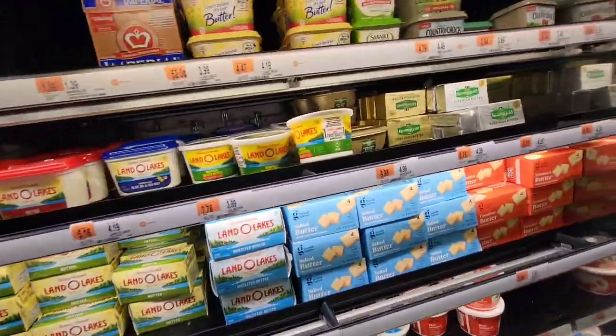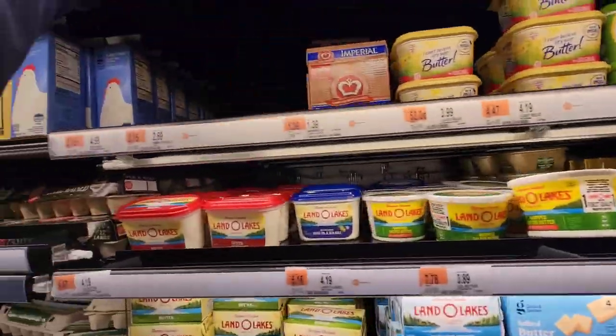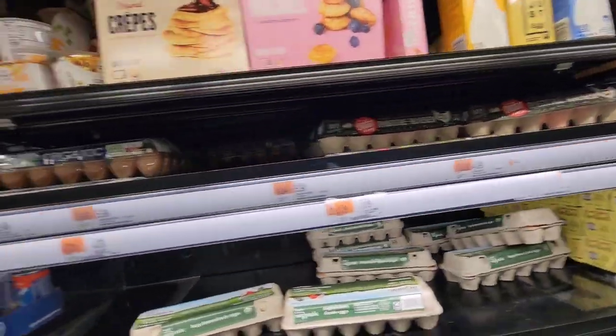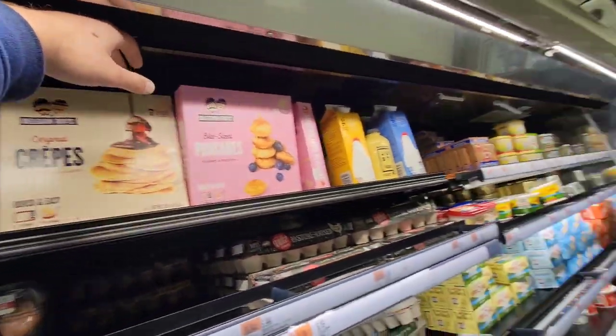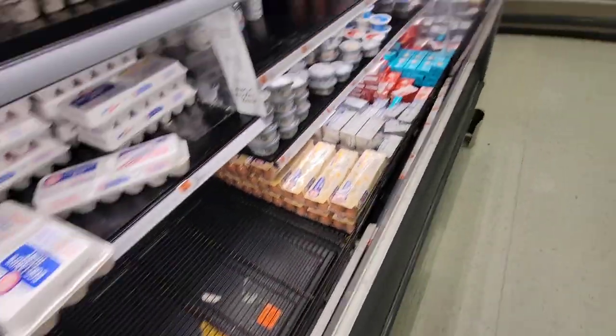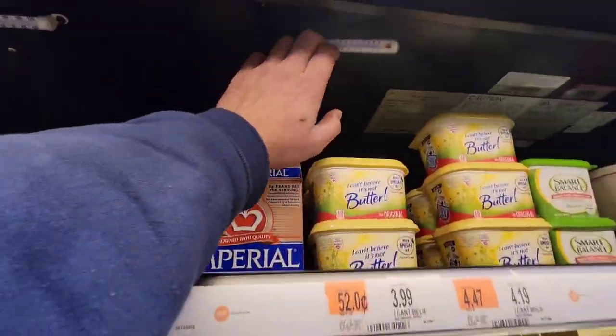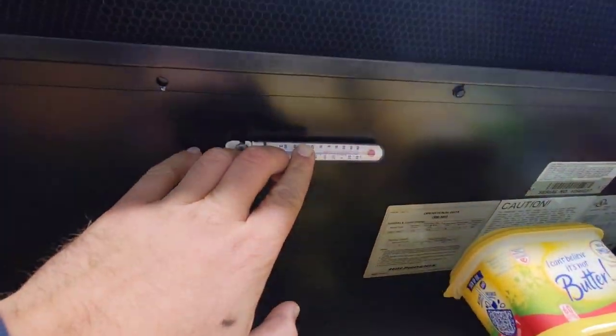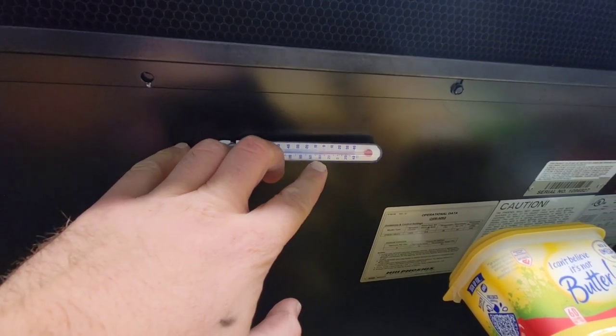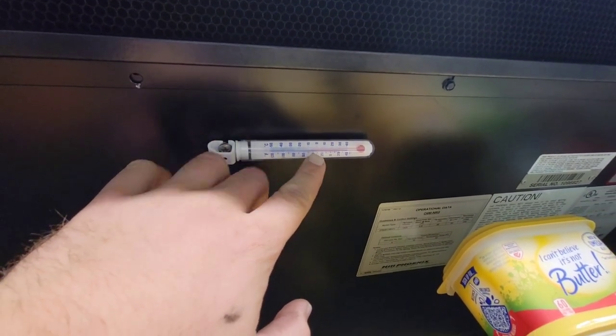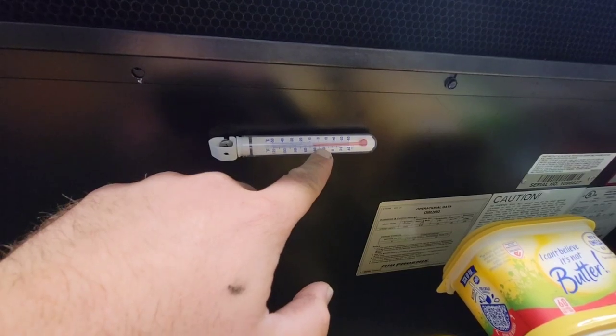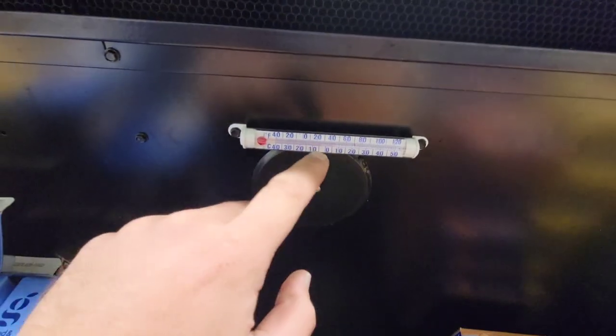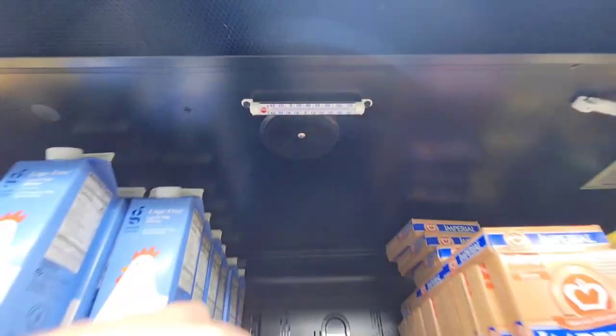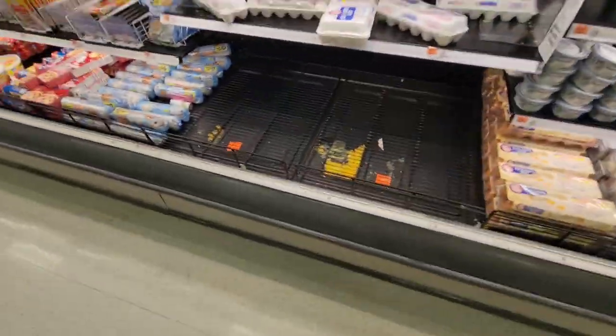Anyway, so first thing is we're just going to check airflow, see how it's doing. Okay, it seems like a little weak, but it could just be the refrigeration. We're also going to check these, what I would call reference thermometers. So these are not gospel truth, they're just a tool to be used, okay? So about 42, about 42, okay? So we're going to check the fans quick.